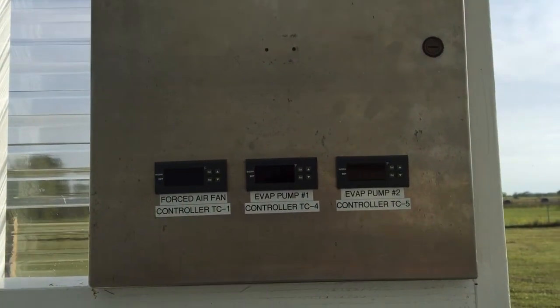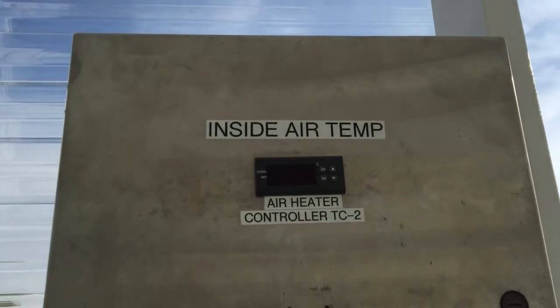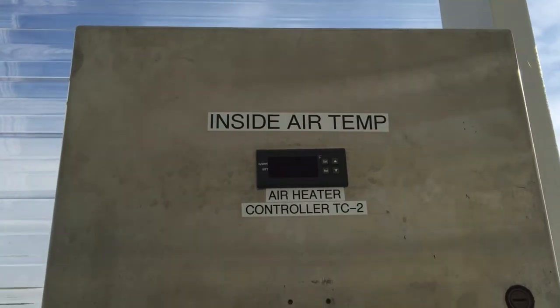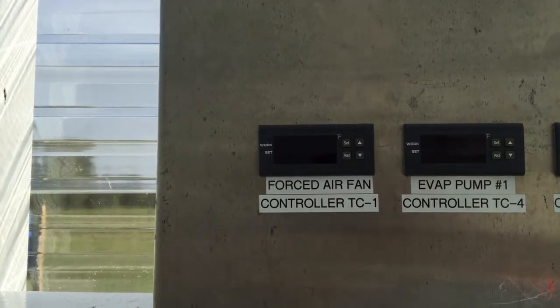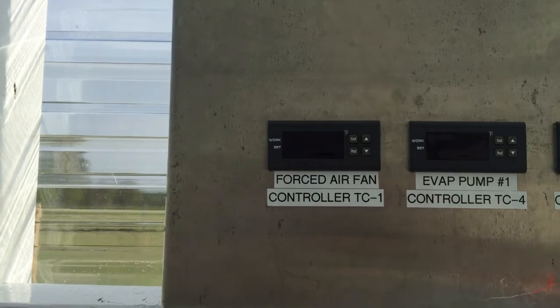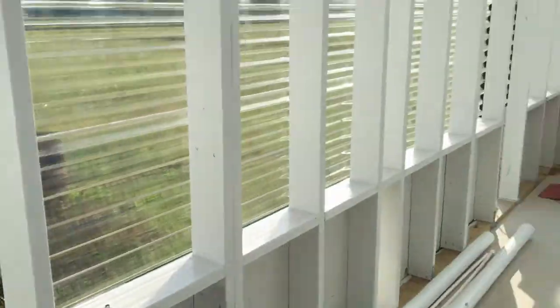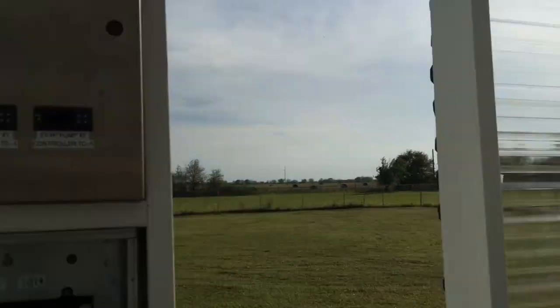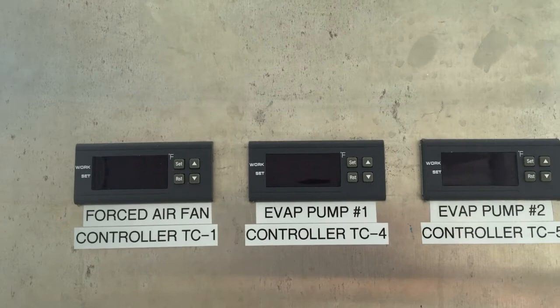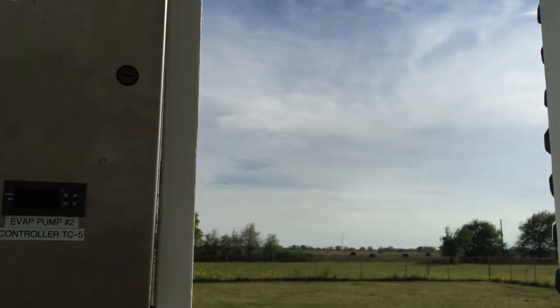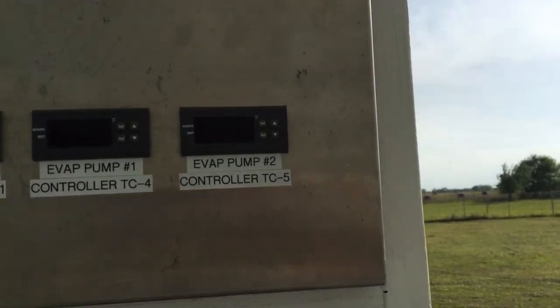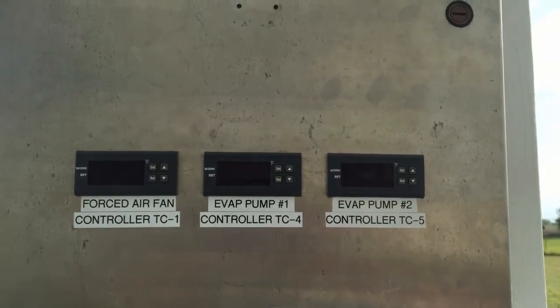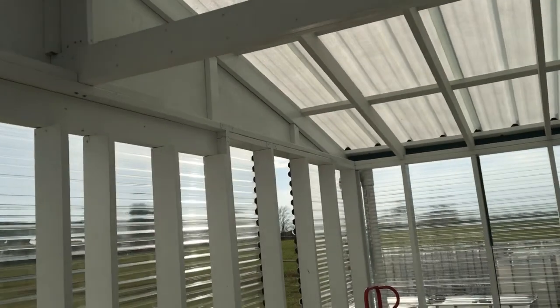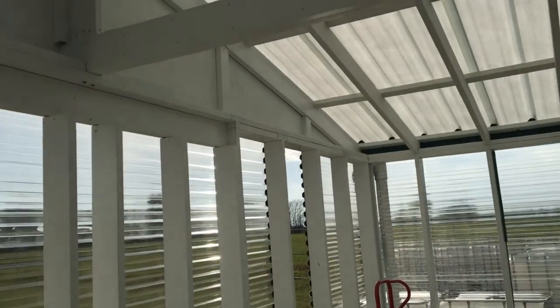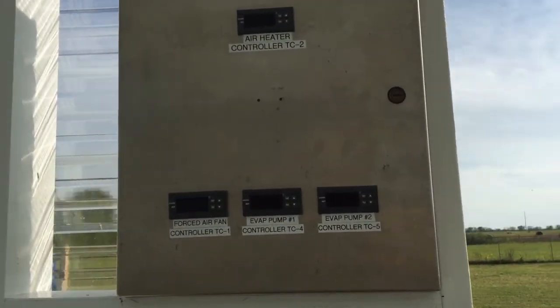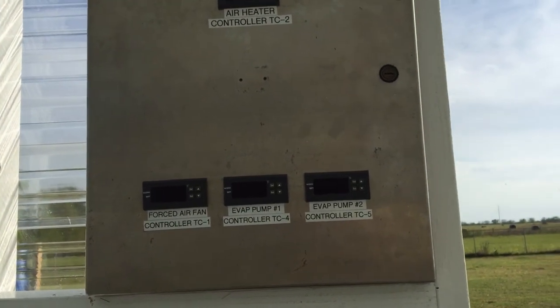All 4 of these are actually reading the air temperature in here. Our main one is going to control the heater if it gets too cold in here. This one right here, when it gets warm, will be the first one to come on, and that'll turn all 6 of these fans on in these 2 evap cooler slots. And if the temperature continues to rise, then this one right here, the middle one, will turn the water in the evap pump on. And if that's not enough, as the temperature keeps going up, that second one will kick in and turn the evap pump on for that section right there. So there's 3 stages of cooling: fans only, and then fans and water, and then fans and water.